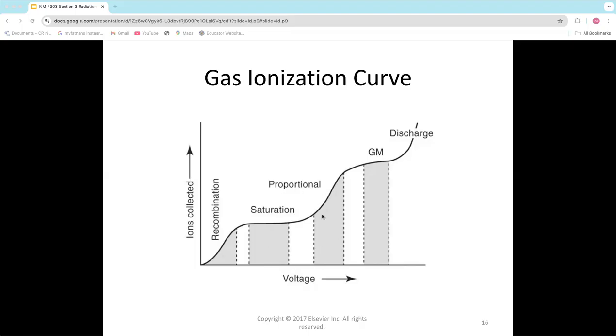Then as we turn up the voltage, we go through a couple of other ranges. This one is called proportional. All it means is that as we increase voltage more and more, we create more and more of the pull of those ion pairs. We don't do a ton in this proportional range. It's mostly the saturation range. But as you increase this higher and higher, you get up to the GM range. When we talk about Geiger-Muller counters, that's what GM stands for.